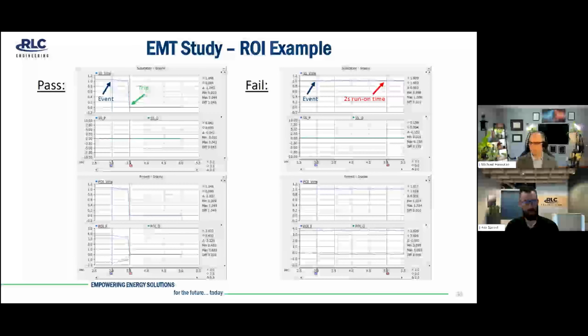Now, to add some color to this, I provided a few example plots here directly from PSCAD. So what you have here on the left is SS, which stands for substation, VRMS or RMS voltage. And then you also have P, real power, and Q, reactive power. Those same three parameters are captured at the POI or the project point of interconnection. So what's captured in these specific traces is you have an event at 3 seconds, which would effectively be one of your upstream protective devices tripping. And then at 3.5, or 0.5 seconds later, the project actually trips offline, and you can see that the voltage goes to zero as you would want to happen under a fault condition or your protective devices opening.